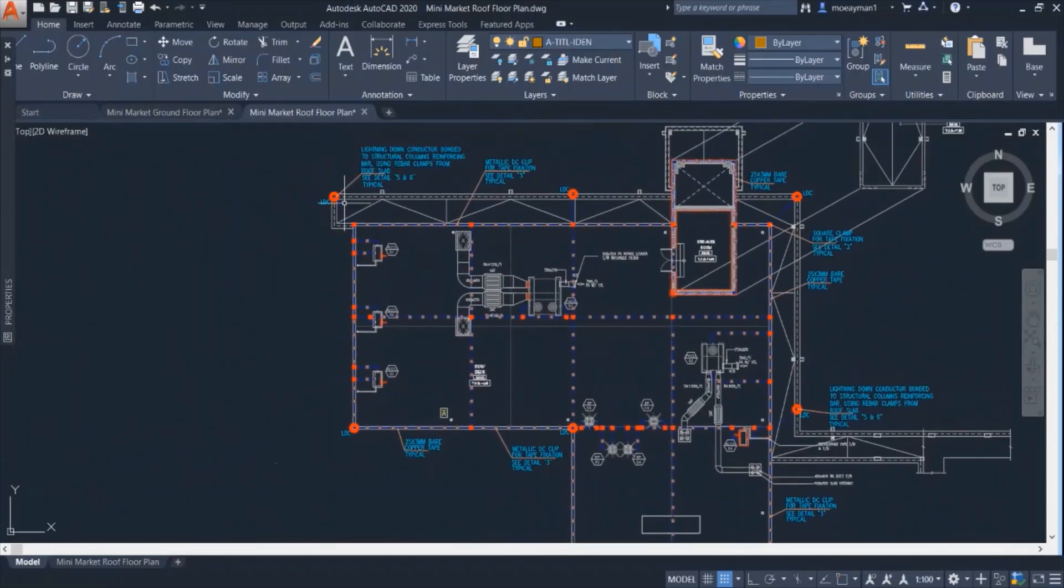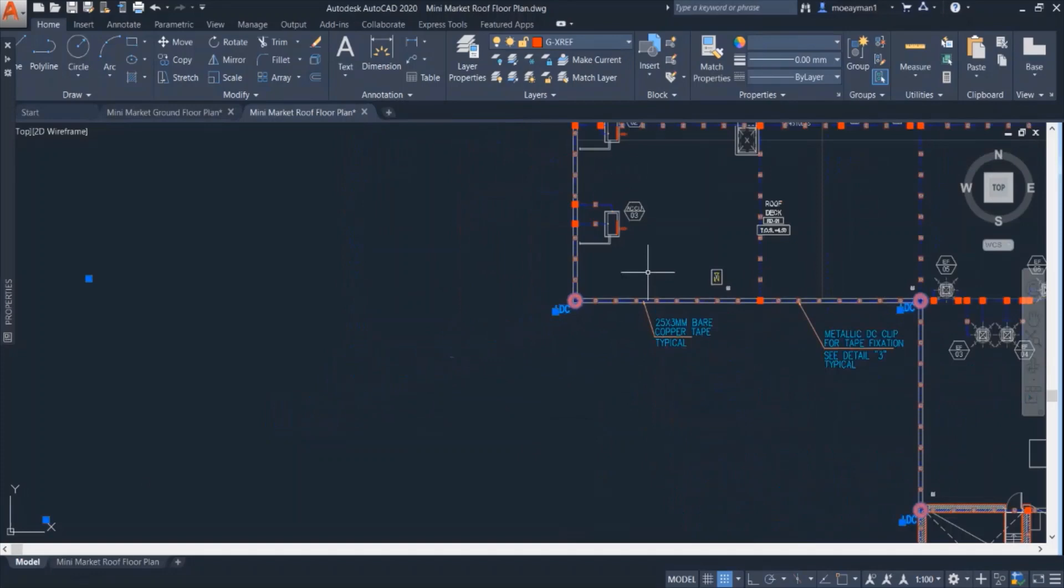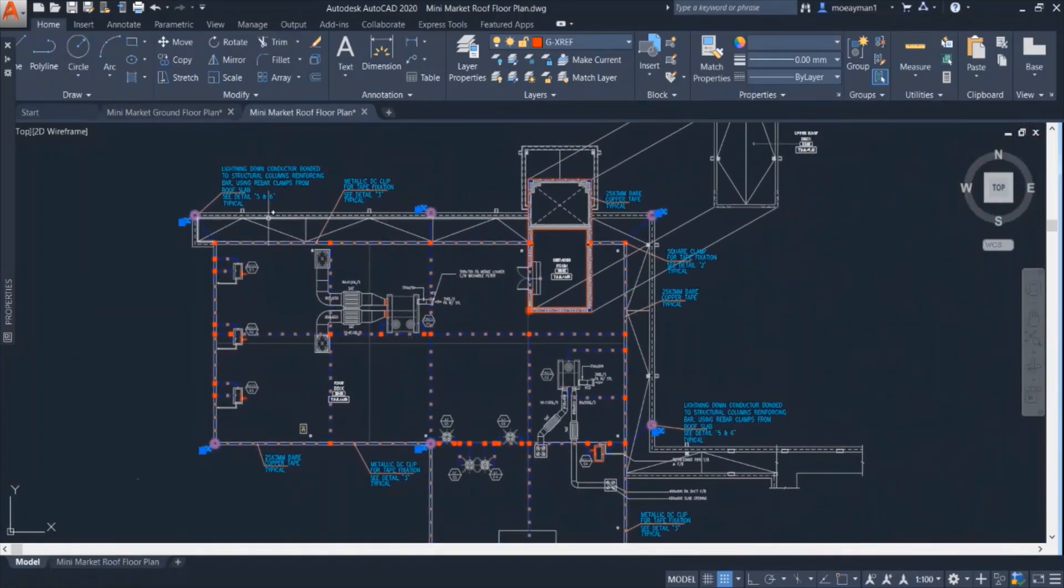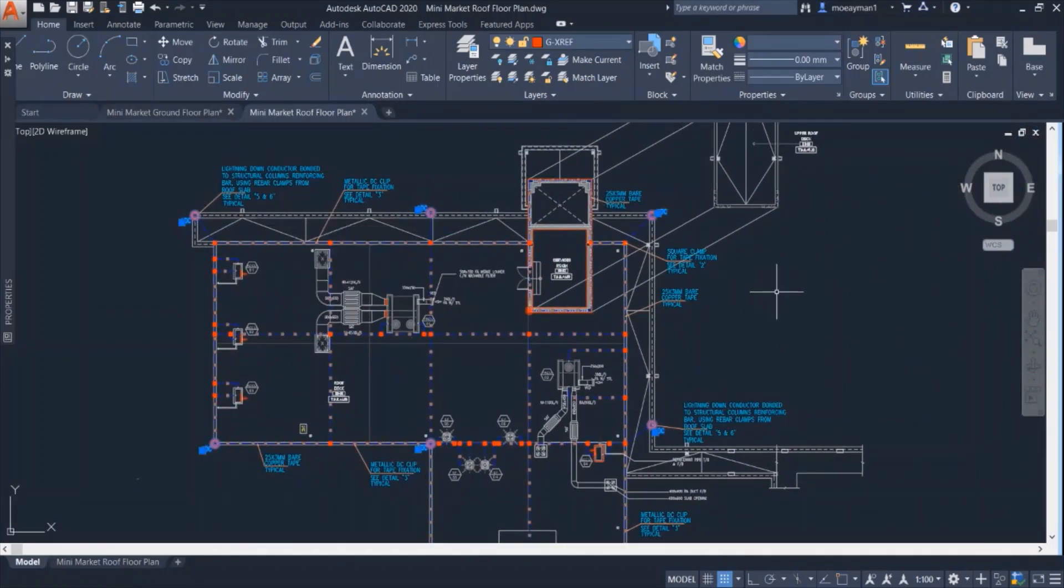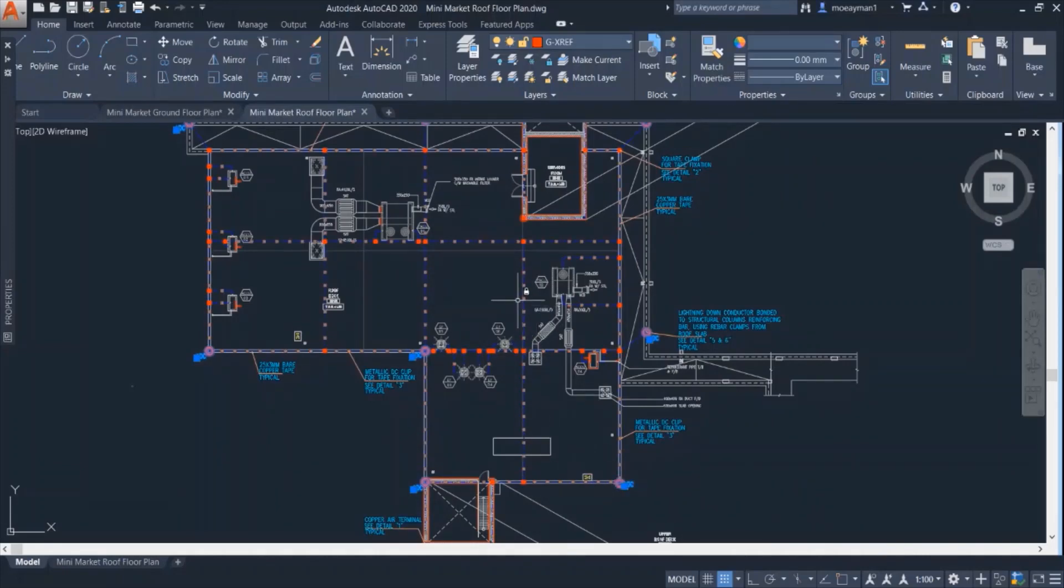We can see here several down conductors. So we can see here that there are several down conductors that are placed symmetrically at each edge of the roof. So where we can find the air termination network or the attracting rods.